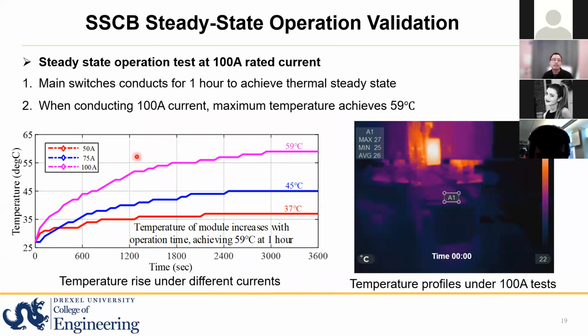Here's our test about the temperature. We tested for 1 hour, from 0 seconds to 3,600 seconds, at different current levels. At first we wanted to be safe, so we started from 50 ampere, then 75, then 100. We can see the case temperature, at the edge of the power module, reaches 59 degrees C, which is kind of acceptable.